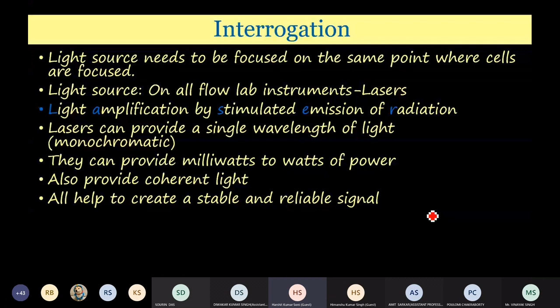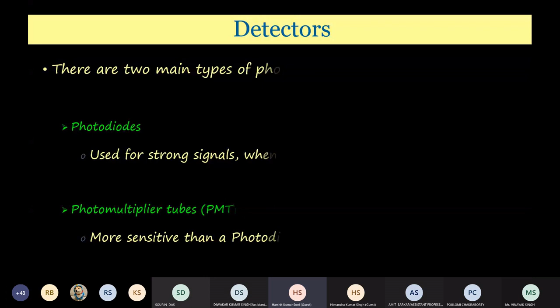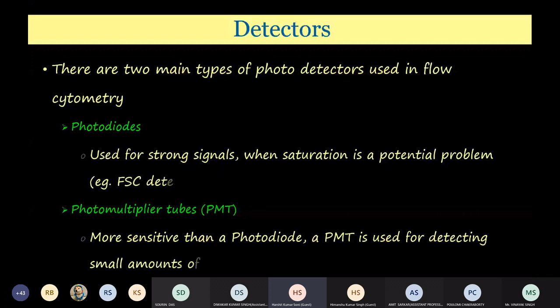Then comes the detector. There are two main types of detector we use in flow cytometry: photodiodes and PMTs. Photodiodes are used for strong signals, when saturation is a potential problem. So it is always used for the FSC. Whenever we use forward scatter, it is always the photodiode because it is receiving direct light, so we don't want to multiply or amplify that light.